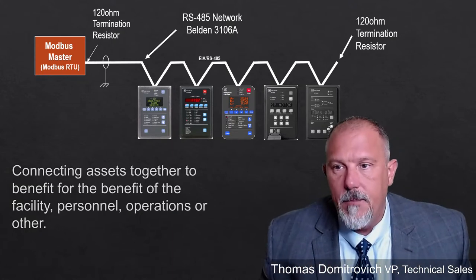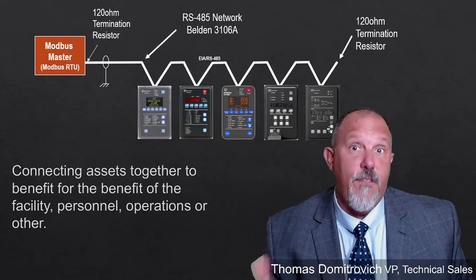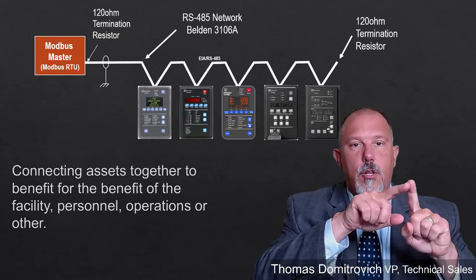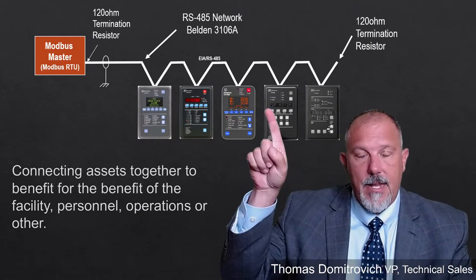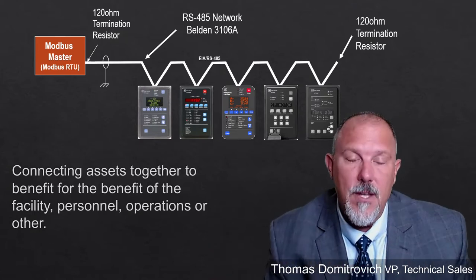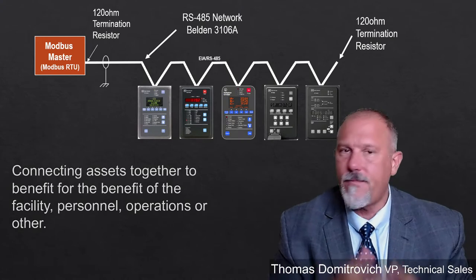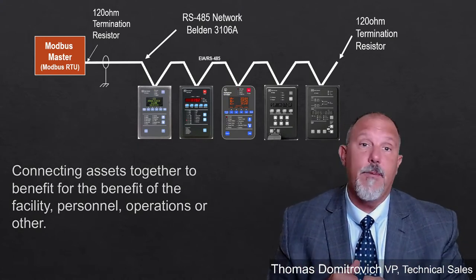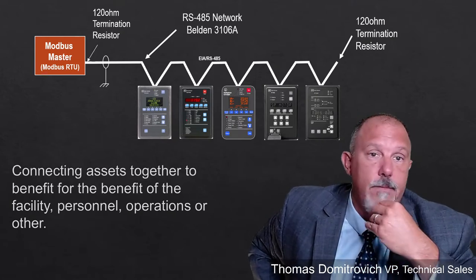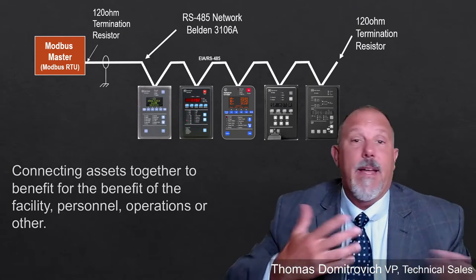So, would a daisy chain backbone for the network be a first choice? I don't know, my thought process, James, is it's a choice, and sometimes it's chosen for you depending upon the devices and the network, the types of equipment that you're buying. I like the ring. With this process where you just have the straight line out and all of those are communicating, if I break a conductor in the middle, then I don't communicate to the rest of them. I just communicate to the first two. There are other architectures, like a ring, so to speak, where if I break anything, I'm still going to be able to communicate. There are different redundancies and whatnot. But a daisy chain, I would say, is probably the most common that I've come across in any Modbus networks, and pretty much even in the proprietary networks, that's the way things have been done that I've seen. That's where my history comes from.